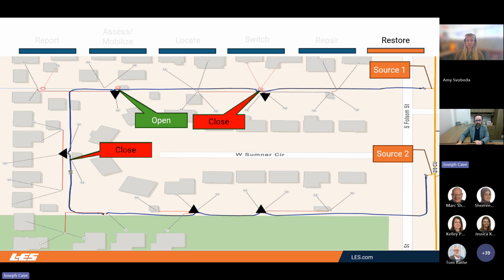You'll see here we still have two open points that were not normally open, and a closed switch that was not normally closed. The troubleshooter goes back out and closes those two points at the transformers adjacent to the failed equipment, then reopens the normal open point, so the entire system is back to the state it was before the outage.